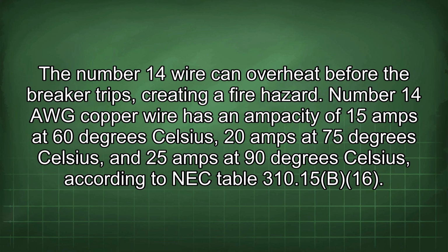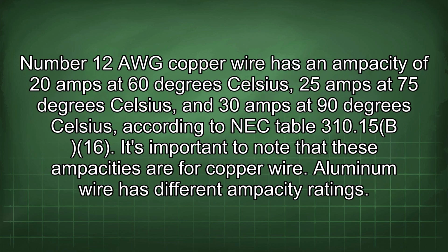Number 14 AWG copper wire has an ampacity of 15 amps at 60 degrees Celsius, 20 amps at 75 degrees Celsius, and 25 amps at 90 degrees Celsius, according to NEC Table 310.15(B)(16). Number 12 AWG copper wire has an ampacity of 20 amps at 60 degrees Celsius, 25 amps at 75 degrees Celsius, and 30 amps at 90 degrees Celsius, according to NEC Table 310.15(B)(16). It's important to note that these ampacities are for copper wire. Aluminum wire has different ampacity ratings.